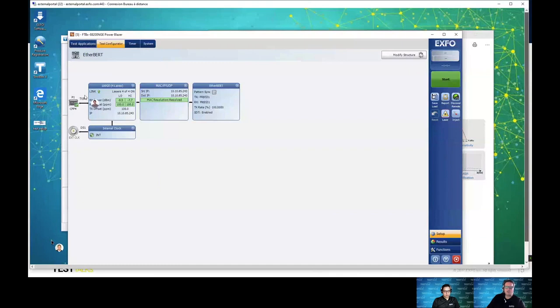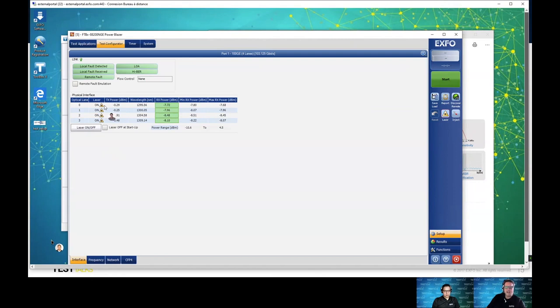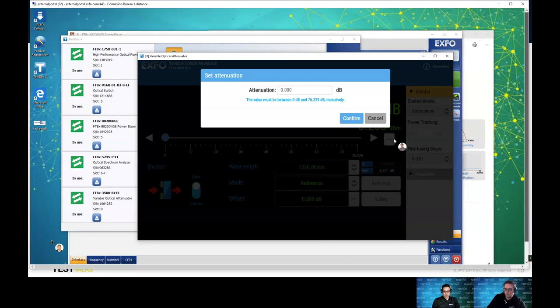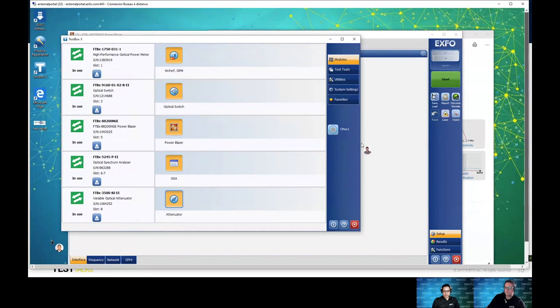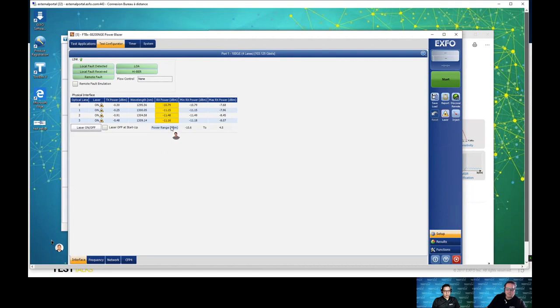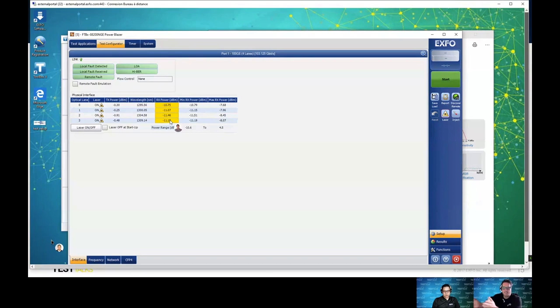And in the online system you do have of course SCPI commands that you can refer to. And then you can, for example, fetch data for bit error. So this is very easy to automate into, let's say, a scenario where you want to test multiple ones, one after another. The next one will be, Aldo, before I go there, I'm just going to switch to save time to the Ethernet BERT. Just probably to highlight that with iOptics, we only need two or three minutes to validate the sample. Yeah that's right. As you saw, it was not very long. It's validating. And any new design, you should use iOptics to validate it. Now after that, what you do is exactly what I'm showing. You do the bit error rate, and now it's a longer test.